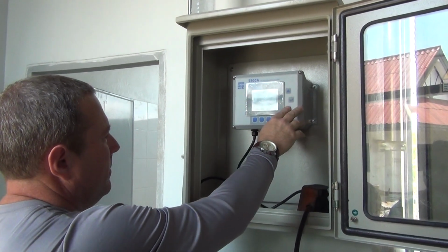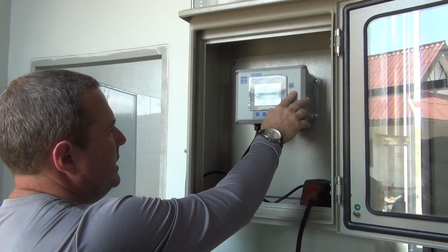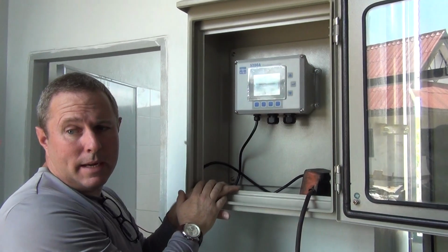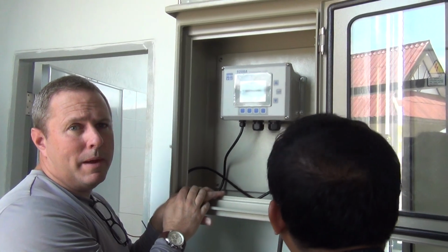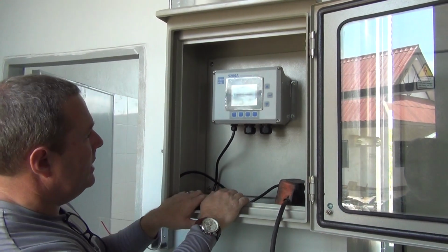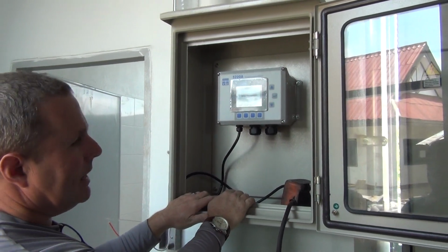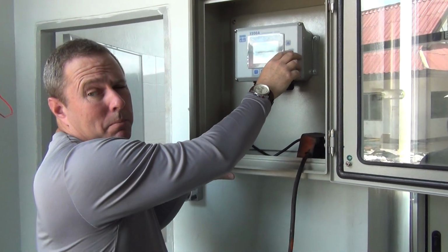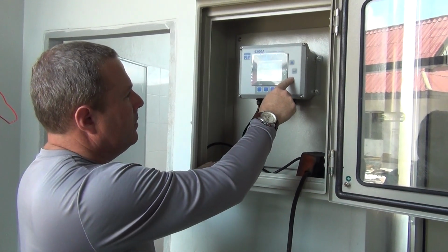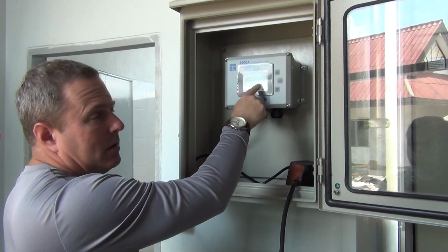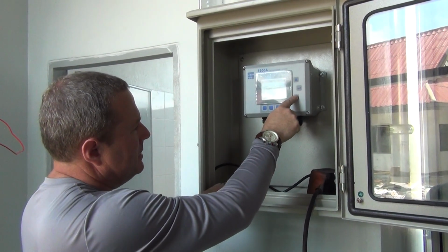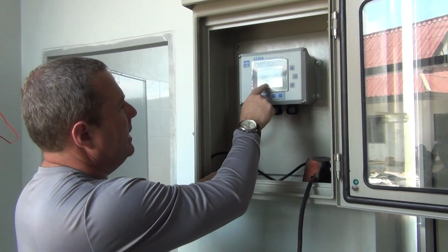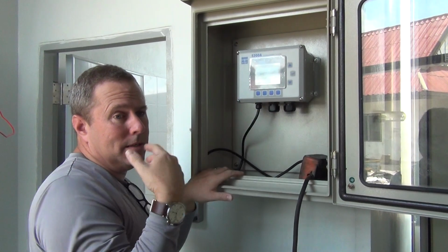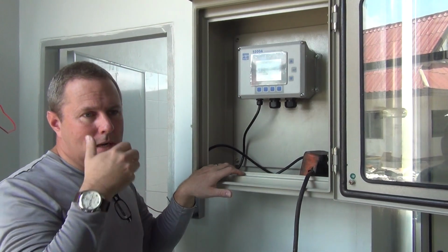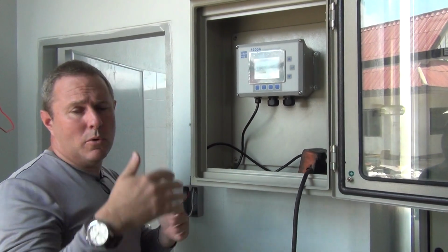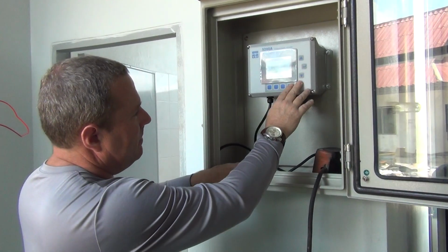The first one, for the DO, I am going to change the membrane type. It defaults to a blue membrane, which is a membrane that is made out of polyethylene. We don't use these very often because they foul. So you have gray membranes which are made from Teflon and they last longer. So I'm setting that to that. The sea level elevation is 0 to 100 feet because this is in English, not in metric. So from 0 to 30 meters. So this is okay, I don't need to change anything.